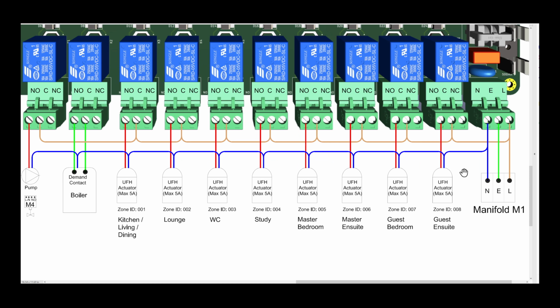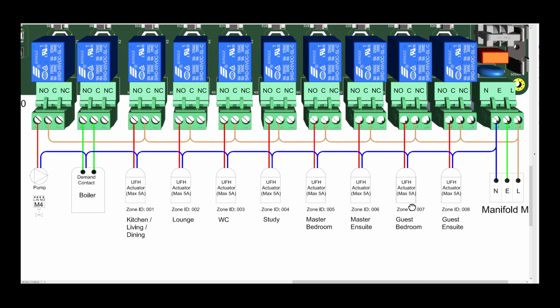Okay, so here we can see a bit larger, and here we go. So we have power supply 110 to 240 volt AC. We have 8 zones, so each zone has a heating output. It's a volt-free contact, which means you can have normally open and normally closed connections if you need. So here, for example, we're showing underfloor heating where all the zones are the same voltage as the main voltage, and therefore we daisy chain from the main to the common connection on each relay. And the neutral is direct to each zone.